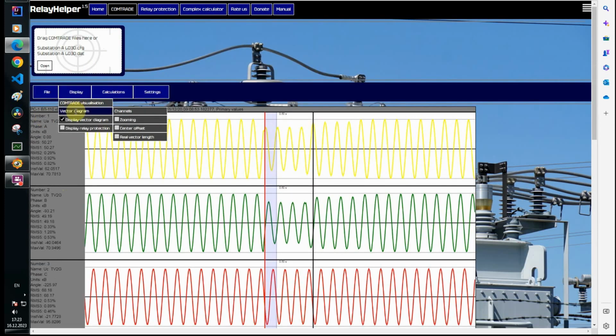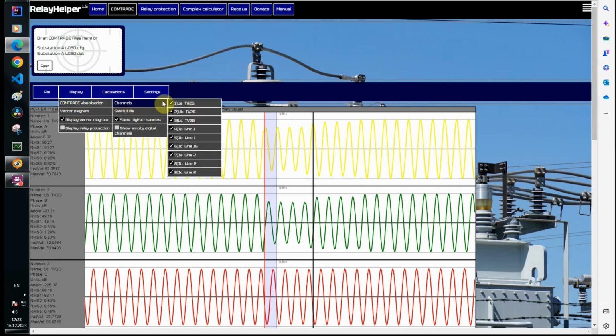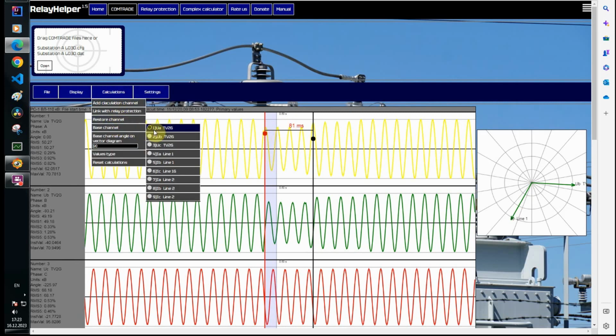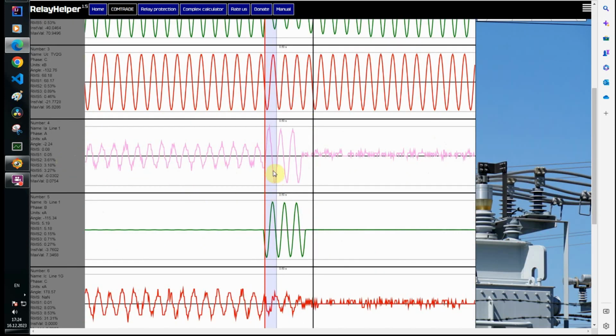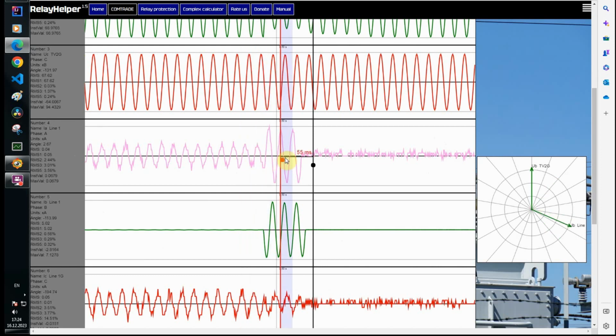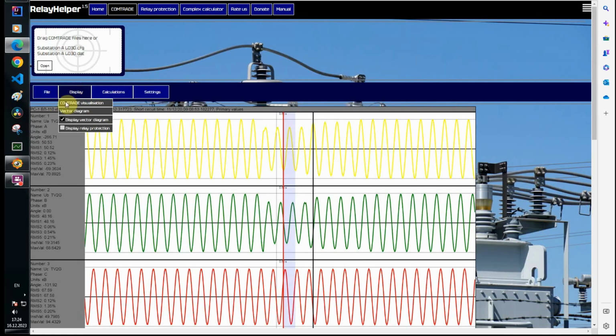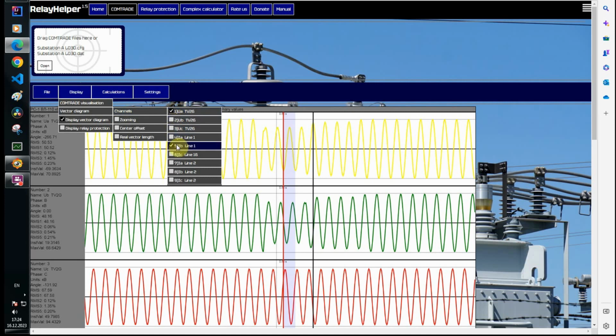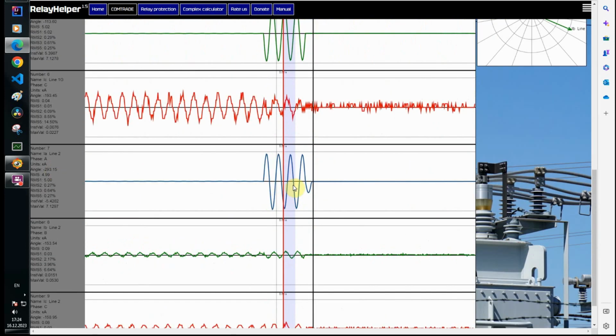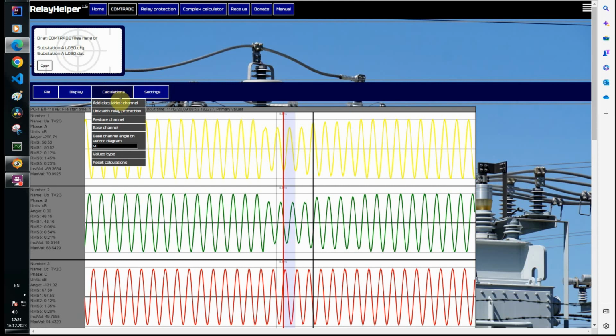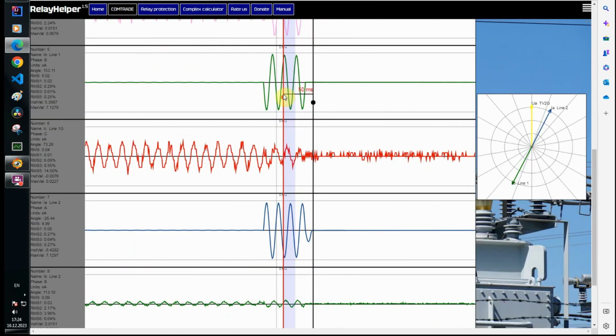Let's look at the vector diagram. I'll add the voltage and current of phase B of the first line. It's like the power is being directed to the bus. Let's see what happens to phase A. And now the arrangement of current vectors from different lines is typical for a 2-phase short circuit.